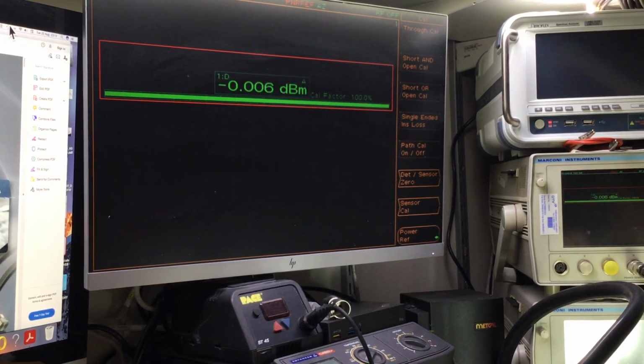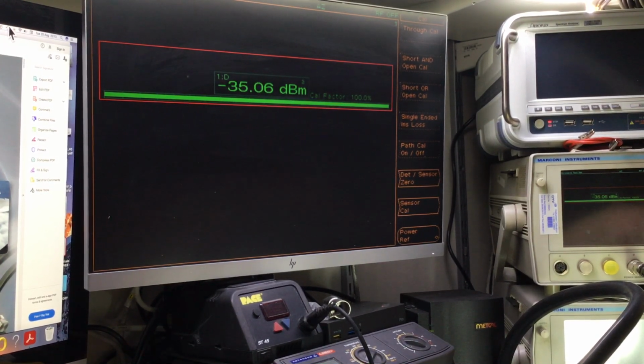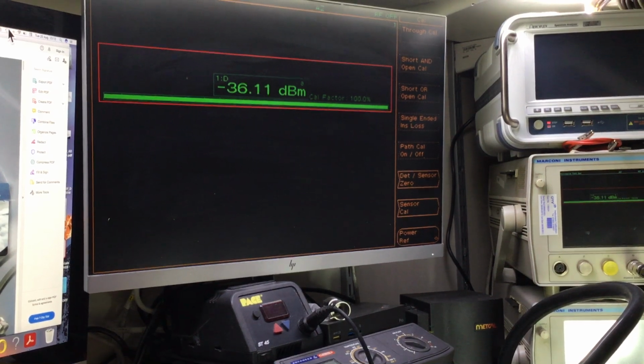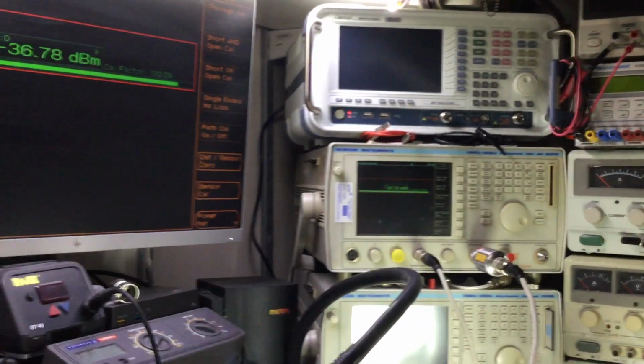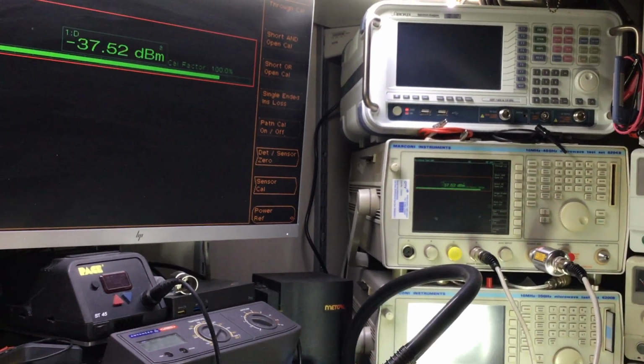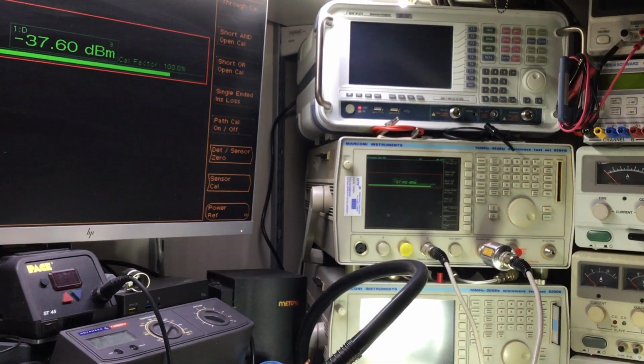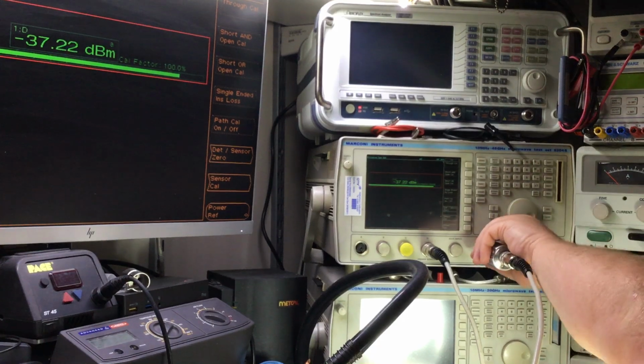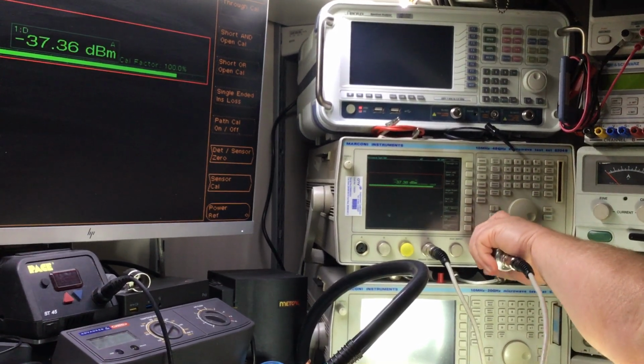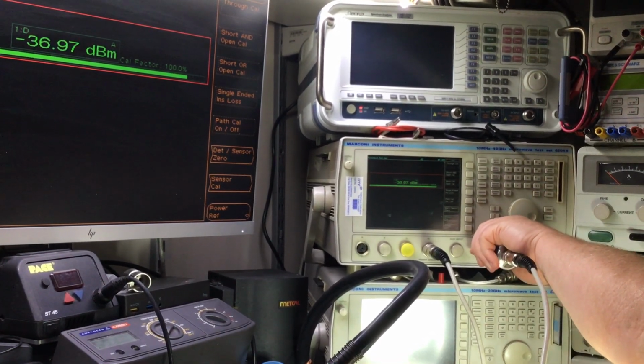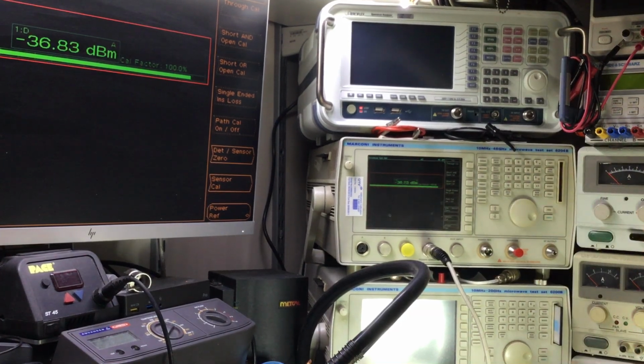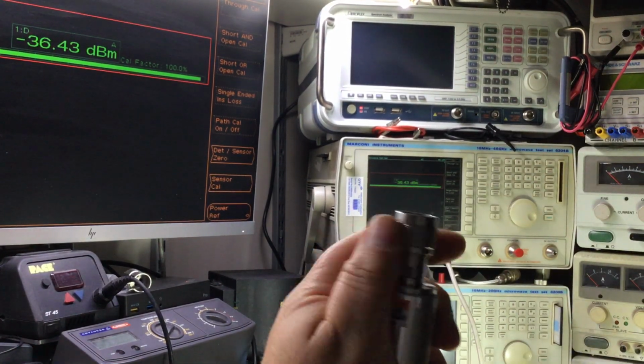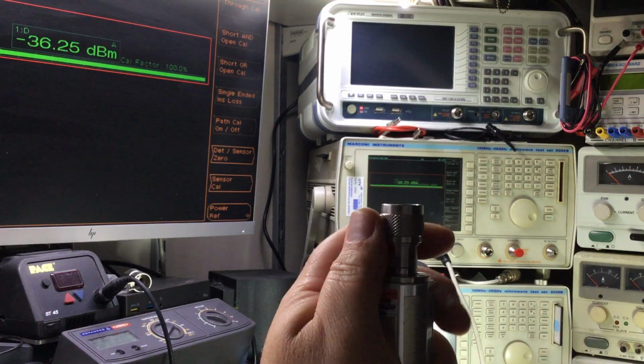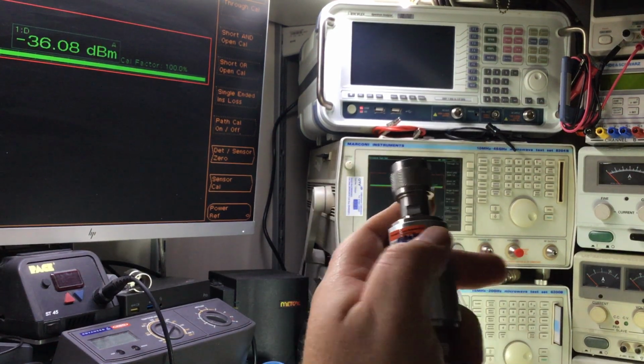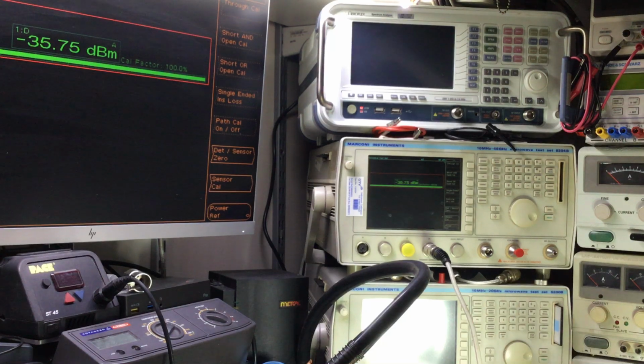Okay, so we'll disconnect that now, and I'm just going to unplug the power sensor there on the front of this Marconi now that we've verified that. Never turn the sensor, always turn the outer collar of the connector, never turn the sensor round. I see people doing that, and it can cause damage to the sensor.